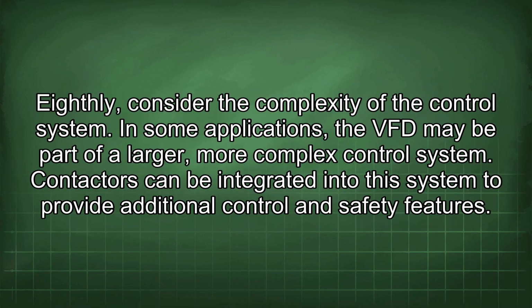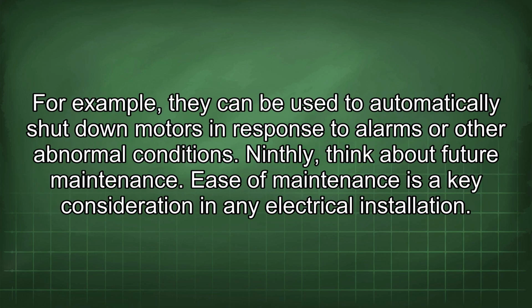Eighthly, consider the complexity of the control system. In some applications, the VFD may be part of a larger, more complex control system. Contactors can be integrated into the system to provide additional control and safety features. For example, they can be used to automatically shut down motors in response to alarms or other abnormal conditions.